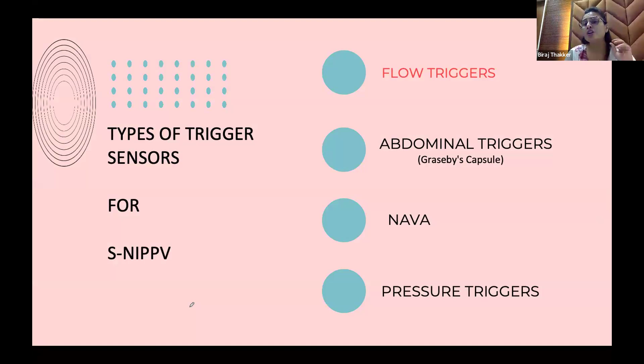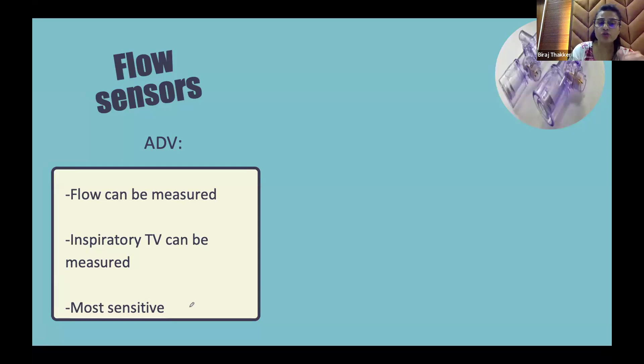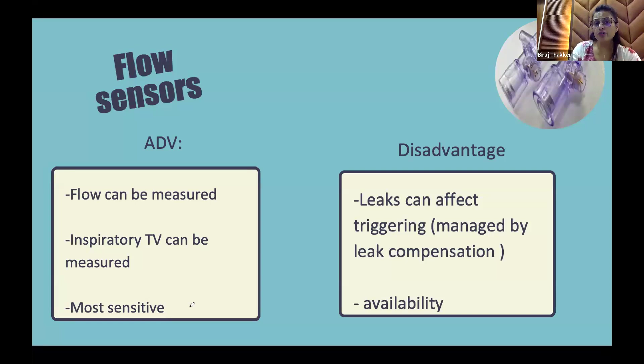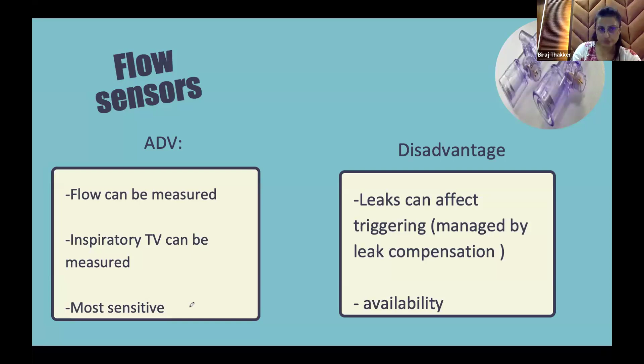There are various varieties of trigger sensors. One is the flow trigger, second is abdominal, third is NAVA, and fourth is the pressure one. The flow sensors measure the flow, and depending on the change in the flow, the breaths are detected and triggered. The advantage is they can also measure inspiratory tidal volume, and it is most sensitive. But the disadvantage is that leak can affect the triggering, and the main disadvantage is availability. Flow-triggered non-invasive ventilators are very few, hardly 1 or 2.